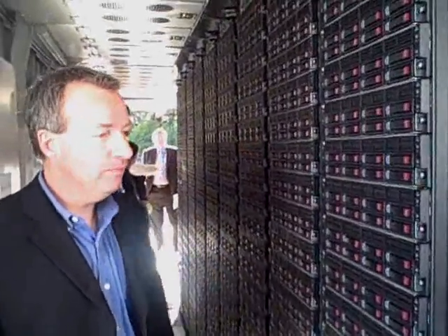The racks of IT would extend all the way down the length of the pod. We've taken some racks out in this case because we wanted to have room for people to come in. We've designed these racks to support any kind of equipment you put into a full-depth 19-inch rack in your data center — so it's not just HP equipment. You can put in Dell, IBM, Sun, etc. We heard very clearly from customers: don't ship a container that only supports HP equipment or only supports blades. Unlike competitors' pods, we'll support third-party equipment.